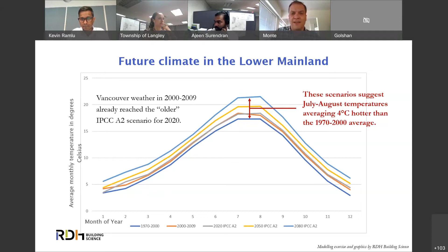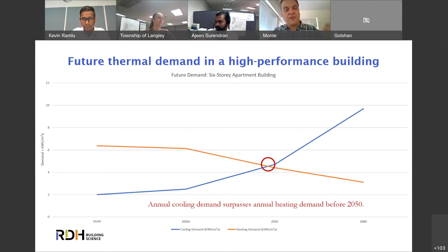So much so that when we look at a high-performance building, such as a Step 4 or Passive House apartment building - this is a 6-story wood frame building in Vancouver that this was based on - notice the heat load, the annual heating demand, drops very slightly because we don't see much loss of annual heating need, but the cooling load rises quite quickly. By mid-century - and we're already seeing it start to happen even though we're years away from 2050 - this will be a cooling-dominated building, meaning annually there'll be more cooling required than heating required.